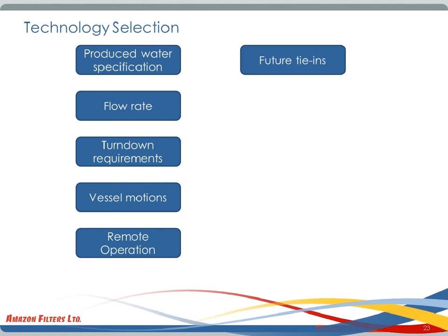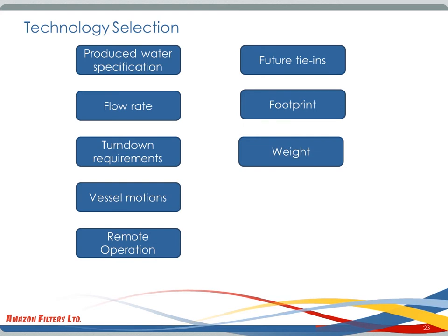Also, the potential for future tie-ins, as we see marginal fields being developed by tying them back to existing processing installations, be they floating or fixed. So it's important to look at what processing requirements would be if any nearby known marginal fields were to be developed later on, and if the economic cost or technical challenges of incorporating that flexibility are not too great, then that is a factor to consider in the design planning for the future.